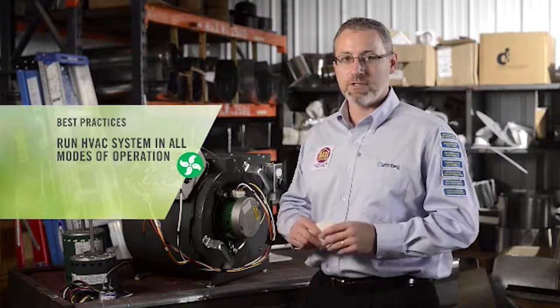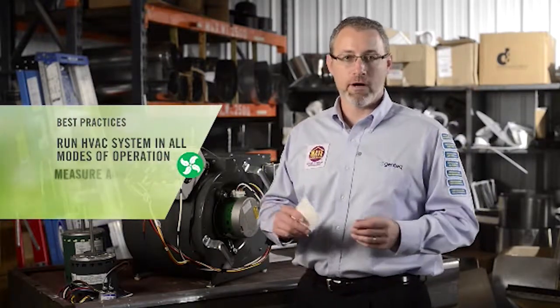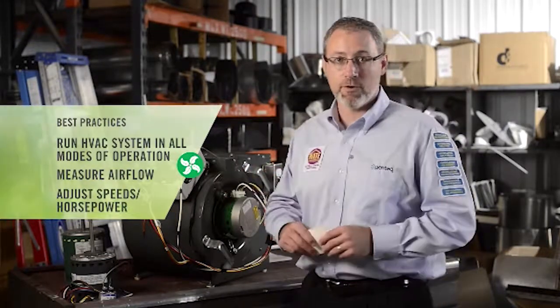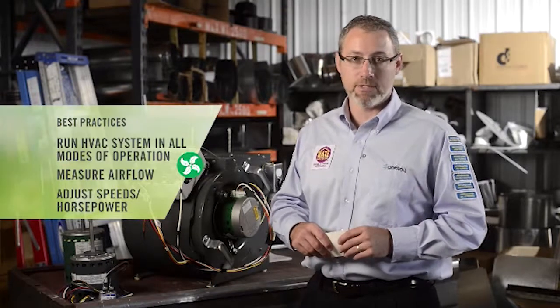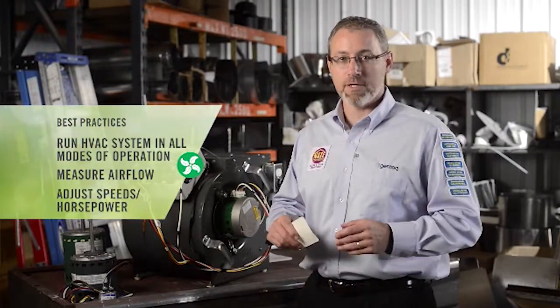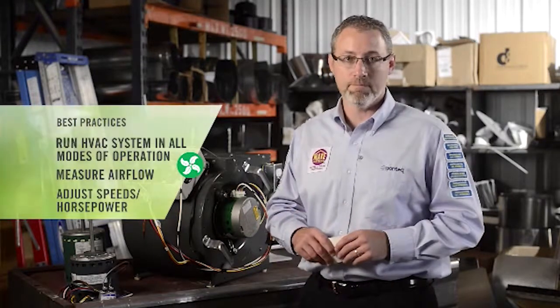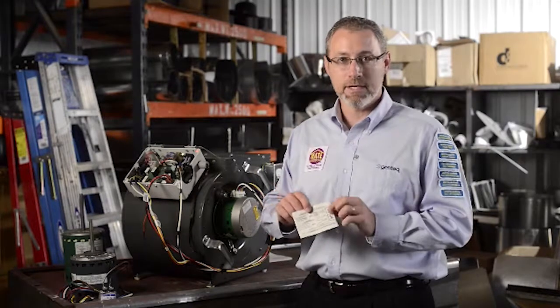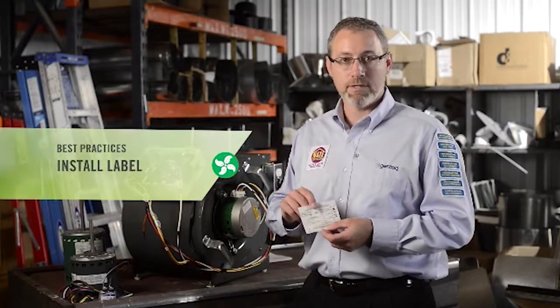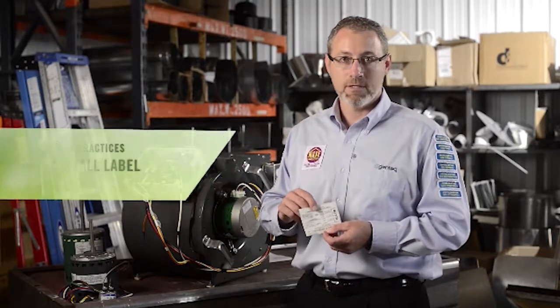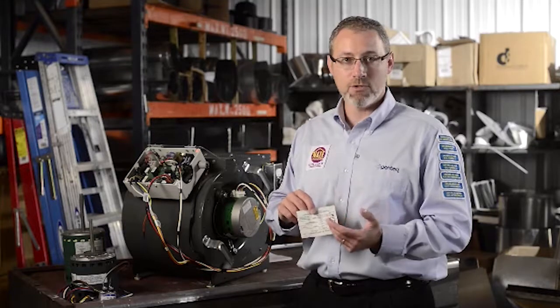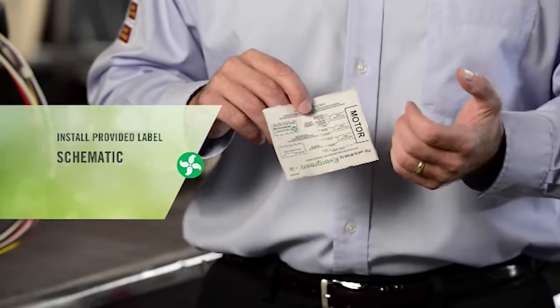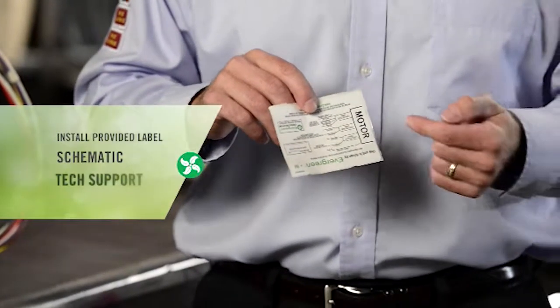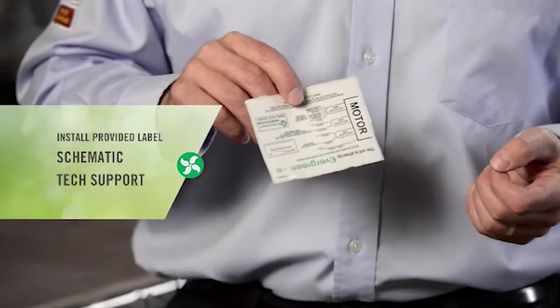Now that we've completed all of our wiring connections and you understand completely how the Evergreen IM operates, the last step in the process is to run our HVAC system in all modes of operation, measure our airflow, and adjust the speeds and/or horsepower that we've set up for the proper operation of our HVAC system, which is an industry best practice after replacing any motor, whether it be universal or OEM. Last but not least, I highly recommend that you take the sticker or decal out of the bag and put it on the HVAC system next to the schematic, so it identifies for the next contractor the speeds, the horsepower, and the wiring for the Evergreen IM that's been connected in their HVAC system. And it also gives them the 800 technical support number if needed.